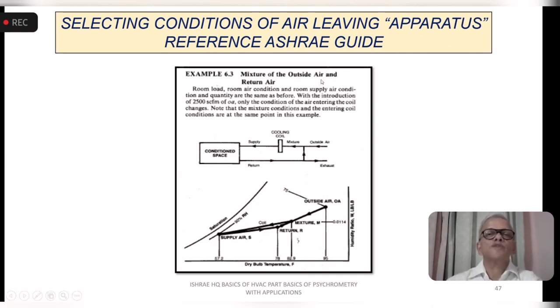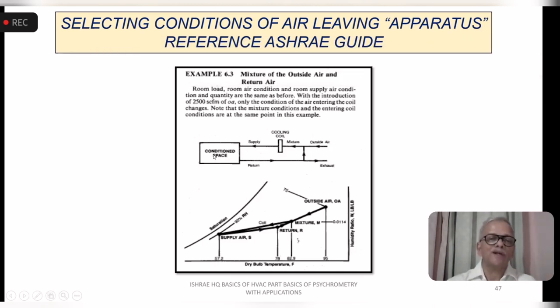Now that's the mixture of outside air and return air, which is most common. So you have outside air, and that is the conditioned space. You have the return air coming from the space, getting mixed with the outdoor air, and the mixture is processed over the cooling coil and supplied to the space. So that is the supply. The quality of this has to be decided by the mixture condition and your desired ADP based on your sensible effect. So what is being done in the conditioned space is undone in the coil, or what is being done in the cooling coil gets undone in the conditioned space.